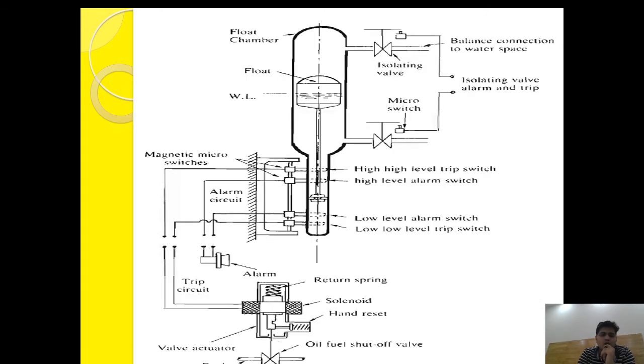If the water level decreases and the fuel supply remains on, the steaming process continues, which will cause the burning of the tubes and damage to the boiler. To prevent this damage, when the water level inside the boiler falls beyond a certain limit, the trip switch is activated.